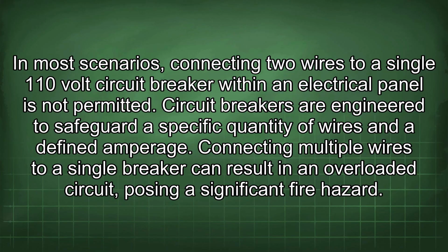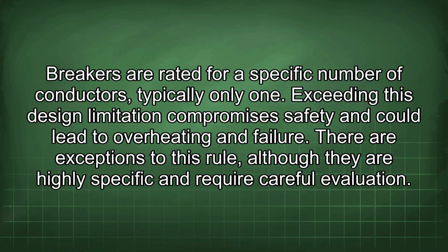In most scenarios, connecting two wires to a single 110-volt circuit breaker within an electrical panel is not permitted. Circuit breakers are engineered to safeguard a specific quantity of wires and a defined amperage. Connecting multiple wires to a single breaker can result in an overloaded circuit, posing a significant fire hazard. Breakers are rated for a specific number of conductors, typically only one. Exceeding this design limitation compromises safety and could lead to overheating and failure.